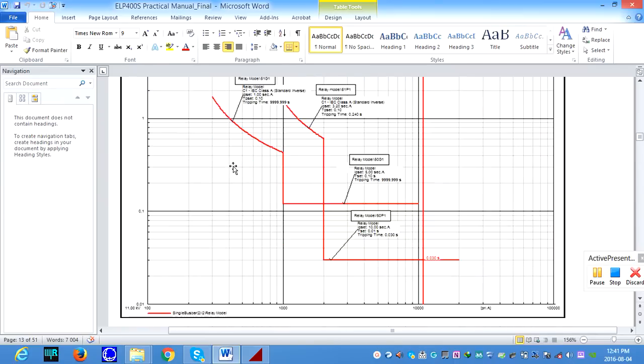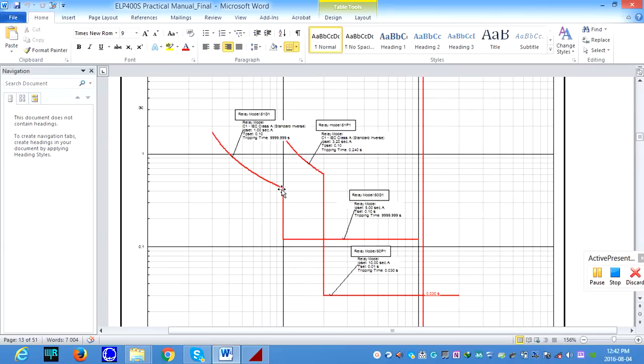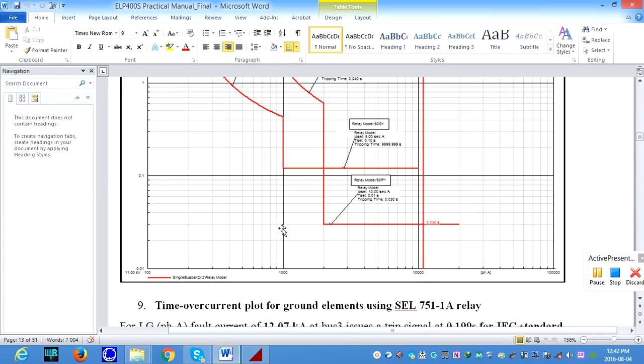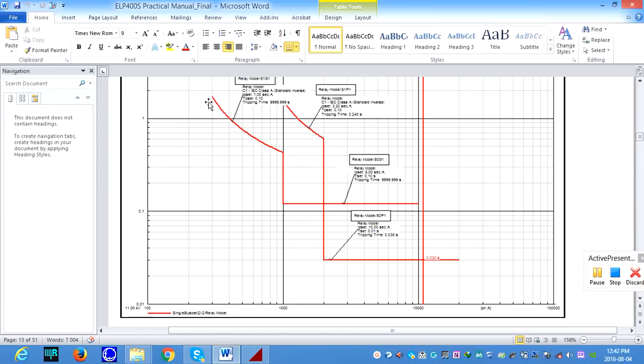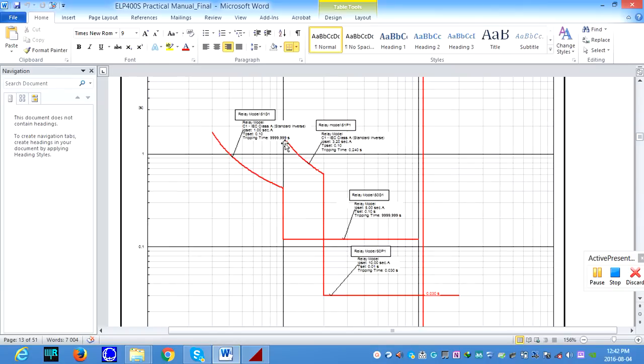And for the ground elements, we already saw the primary current values. It means from 200 to 1000. So from 200 to 1000, you're getting an inverse characteristic. 200 to 1000, this is your 1000. Okay, you see this is 100 and this is 200. That's why the curve is starting from here. 200 to 1000 will be an inverse characteristic. From 1000 onwards, it will be a definite characteristic. Okay, so that's clearly explaining the combination of inverse and definite for the ground element, and the same thing for the phase element. The combination of inverse and definite will give you the characteristics for the phase elements.